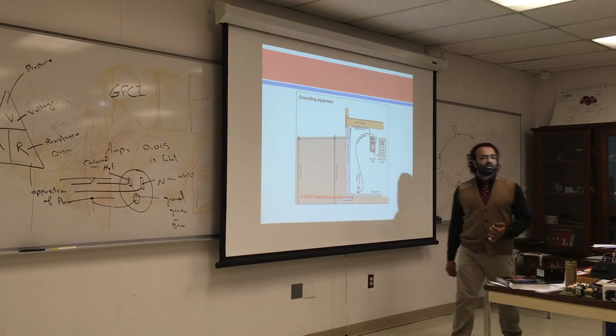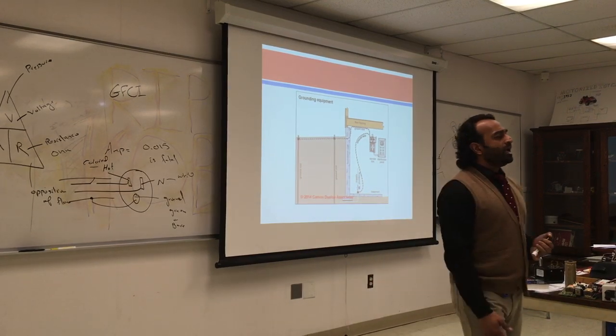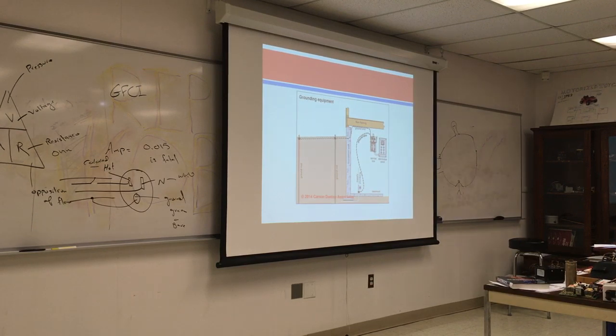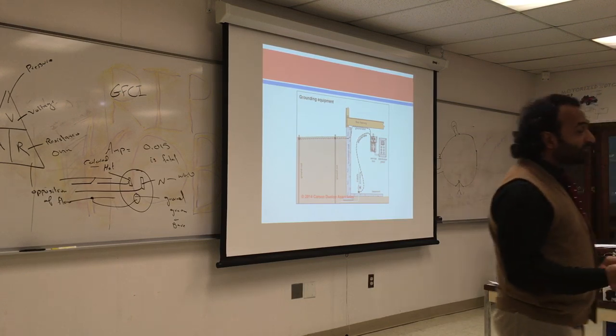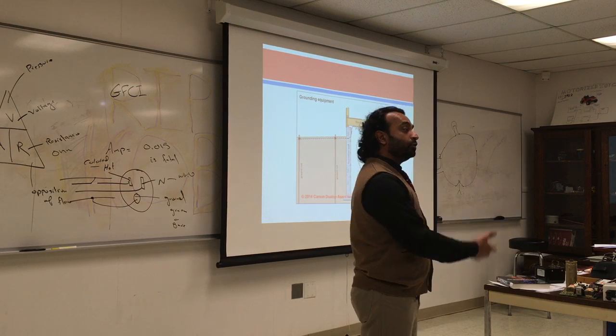A lot of houses have something called knob and tube, an old wiring system. It's not a good idea to enforce new rules in old houses, because not everybody has the money to change things, so most old equipment gets grandfathered in. You'll see a lot of old, ancient equipment in the field, and they used to make it very well. I just fixed a boiler in December that was 40 years old, before I was born. It's still running, it just failed now, and it didn't even fully fail, just one part deteriorated. So you can see a lot of good equipment running with old, ancient controls. That's okay. They're not going to force people to change it, but new installations have to use updated, safer equipment.